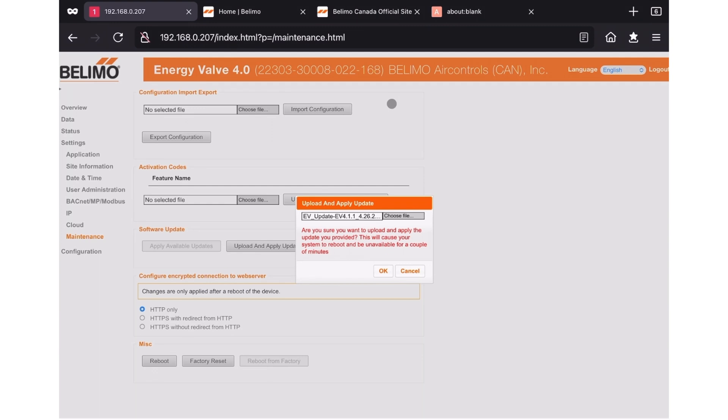Take a brief moment to review the warning message that appears on the upload and apply update pop-up window. If you're comfortable proceeding, click OK. If you're not, click cancel. In most circumstances, your energy valve or thermal energy meter will be offline for up to 10 minutes, so it's best not to do this for critical applications during normal hours.